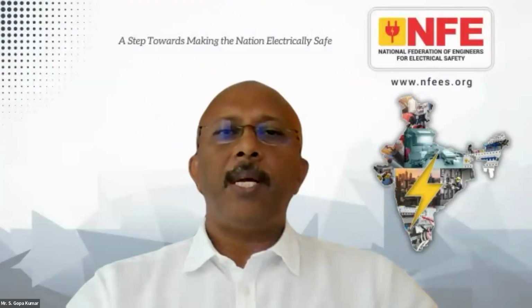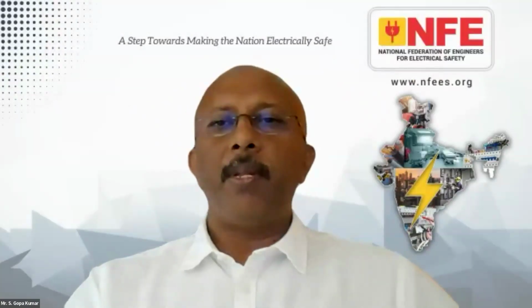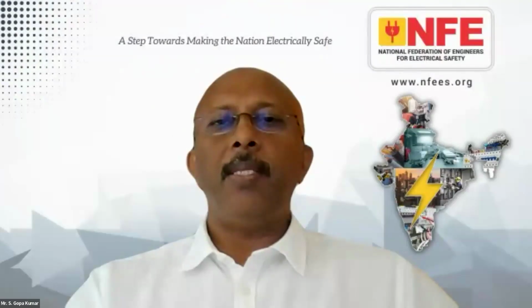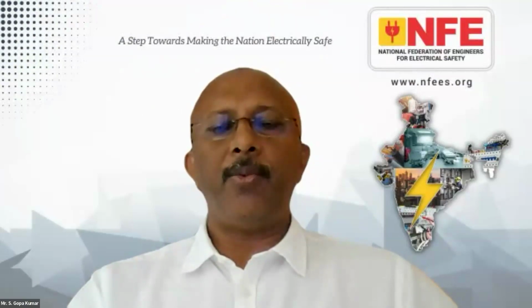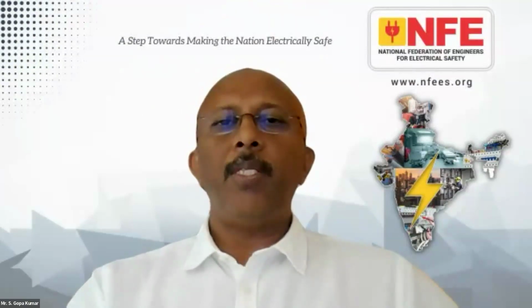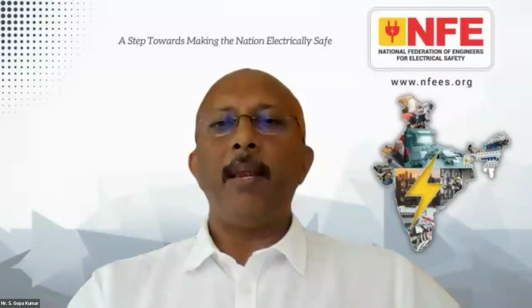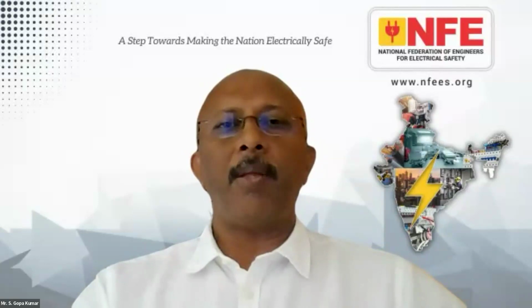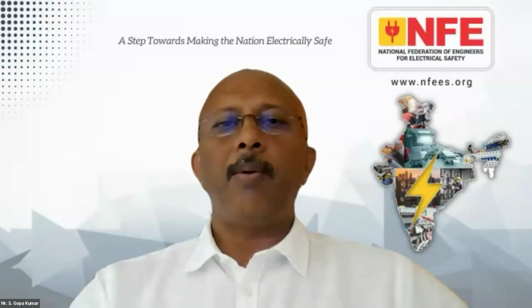Mr. Niranjan asked for a quick comment from the expert on whether multiple earth pits are okay in hospitals. I would like to put it simply: not multiple earth pits — instead, not even one earth pit is necessary for the electrical installation to be safe. That is why IS 732, a supporting document for the National Electrical Code, clearly states that an installation may have an earth electrode — meaning sometimes, for example for lightning protection, you may need one. Otherwise, earthing has nothing to do with the earth electrode in soil; it's a totally different subject. I hope the question is clear — not multiple, not even one is required, is the answer.